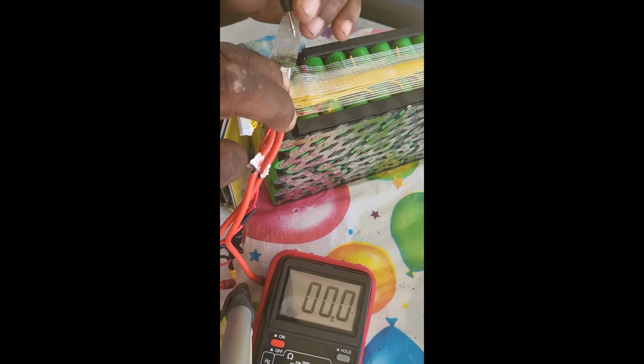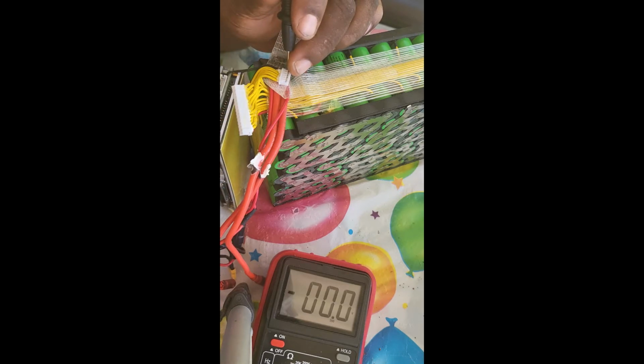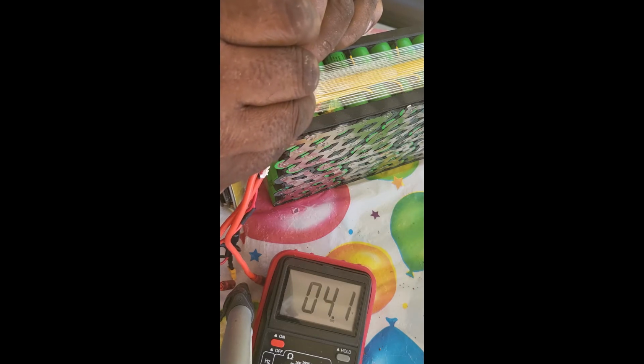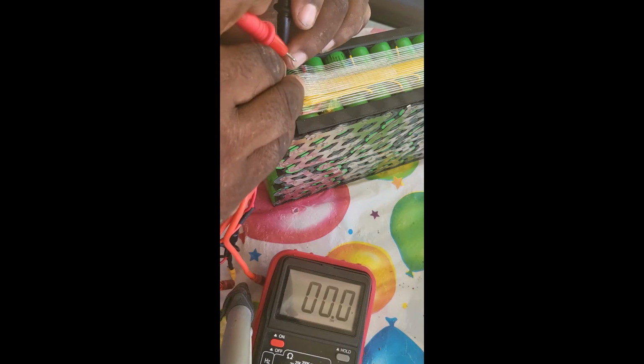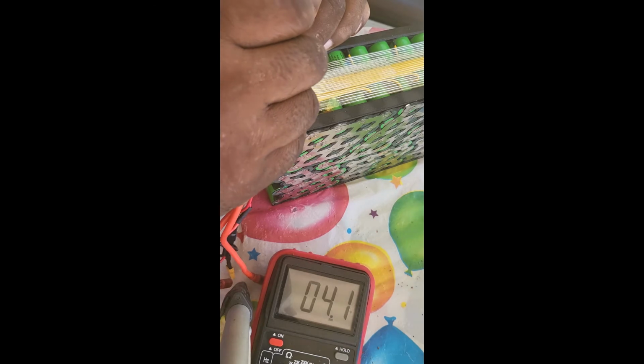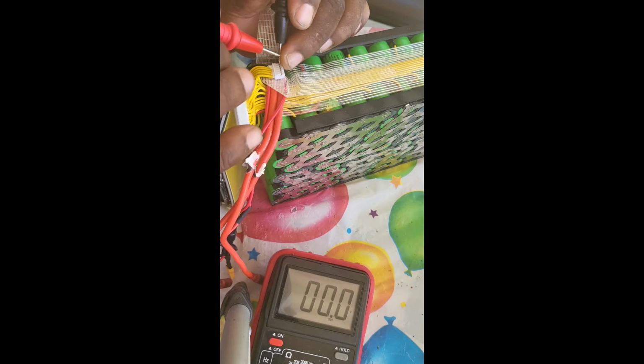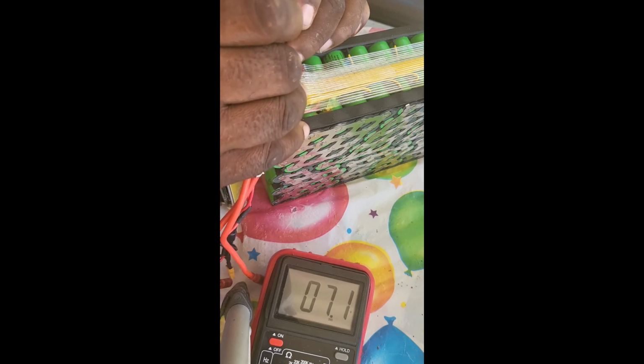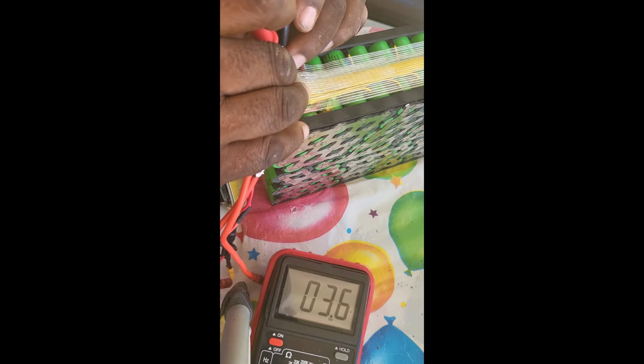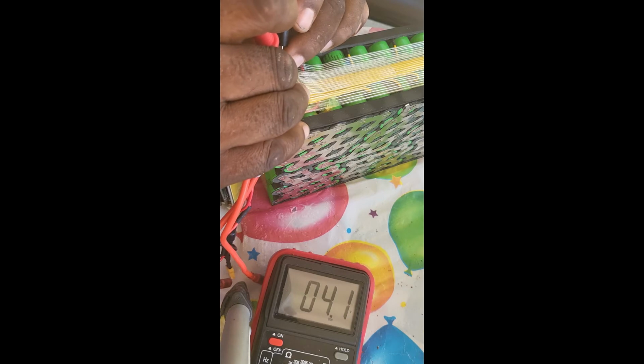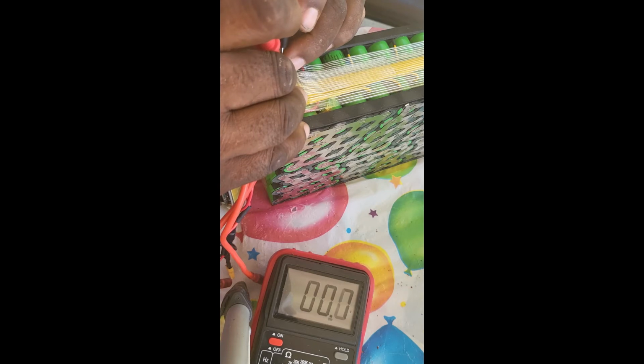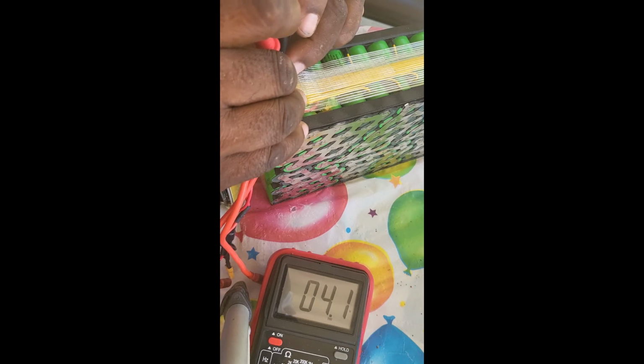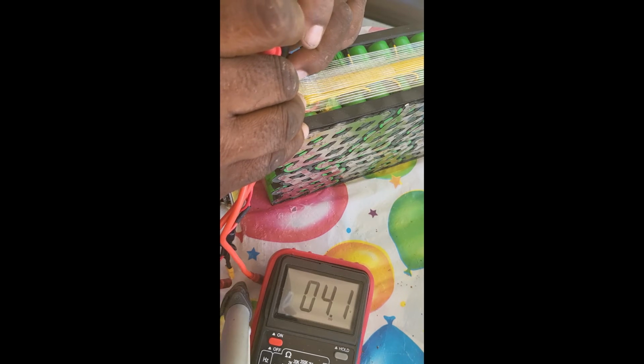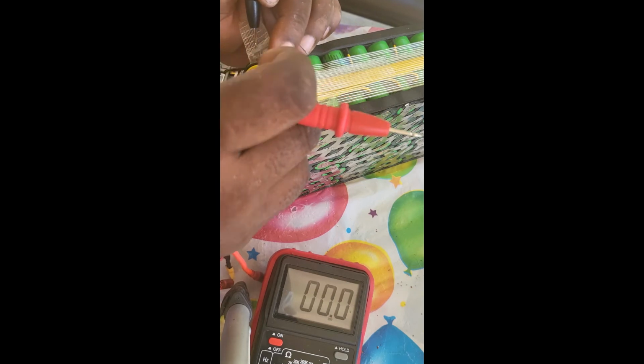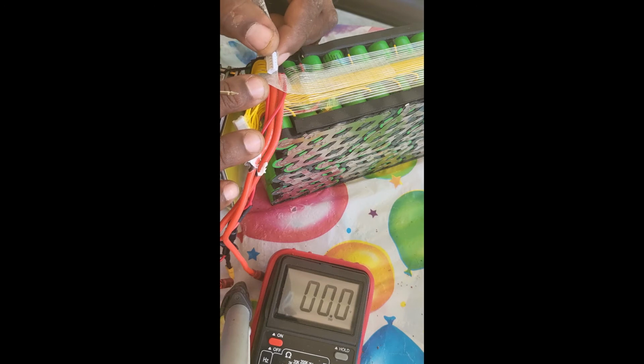To do that, you start with putting your negative probe on a negative wire, then check the one next to it. You should see 4.1 volts. Then move your probe to the next line up, careful not to touch but one wire, and check the second pair, 4.1 volts. Moving up, check the third pair, 4.1. Moving up, check the fourth pair, 4.1. Moving up, check the fifth pair, 4.1. So that's the first little batch of wires, 1, 2, 3, 4, 5.